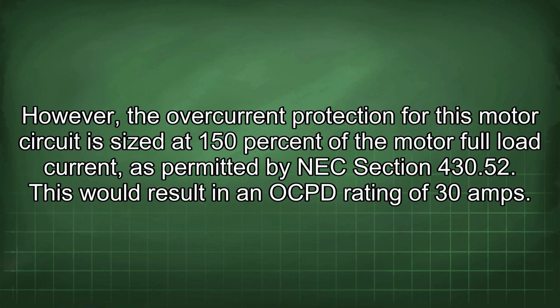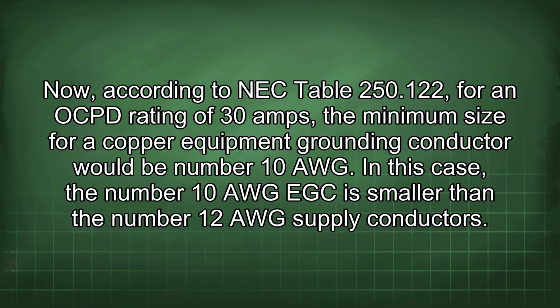However, the overcurrent protection for this motor circuit is sized at 150% of the motor full load current, as permitted by NEC section 430.52. This would result in an OCPD rating of 30 amps. Now, according to NEC table 250.122, for an OCPD rating of 30 amps, the minimum size for a copper equipment grounding conductor would be number 10 AWG. In this case, the number 10 AWG EGC is smaller than the number 12 AWG supply conductors.